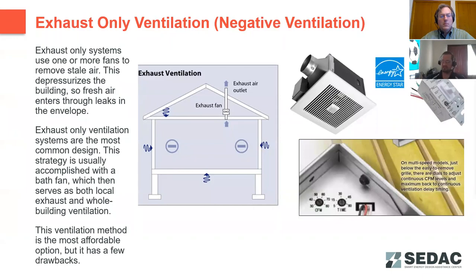Exhaust ventilation only is probably the most common and probably the least expensive option for doing ventilation. We do note, though, that it does have some potential issues in that you're relying on gaps and cracks in your building envelope to replace that exhaust air with fresh ventilation air. And so you do have that potential to draw in moisture into your wall assembly and have condensation issues, things like that. It can be designed effectively, but you have to be very careful with where that air is coming into the envelope and how your envelope is set up to handle those leaks.